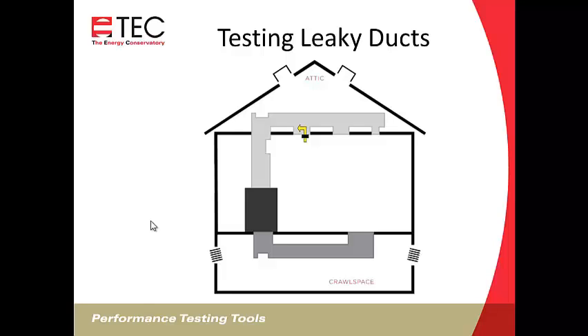Testing leaky ducts. We'll define leaky ducts as greater than 500 CFM. If you're testing tight ducts, which we would call less than 200 CFM, then you're going to be getting pretty stable readings, good representative readings at any of those three locations we just talked about.